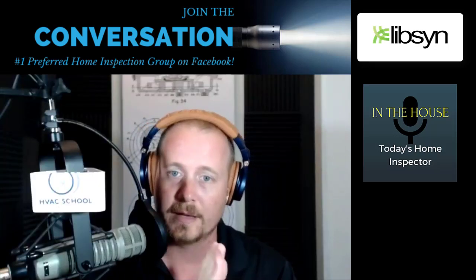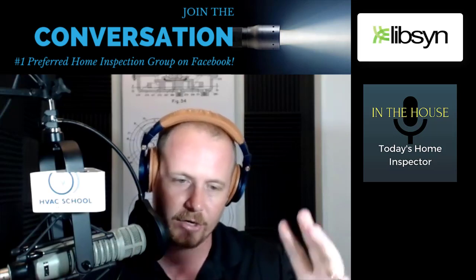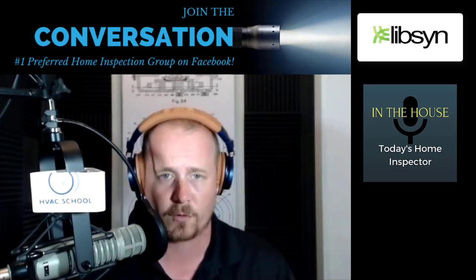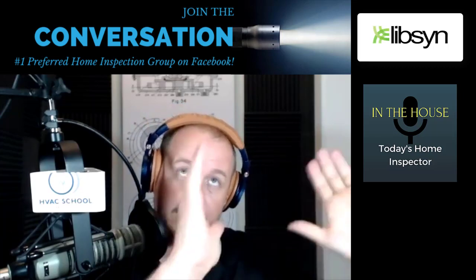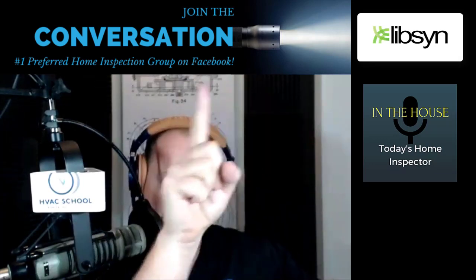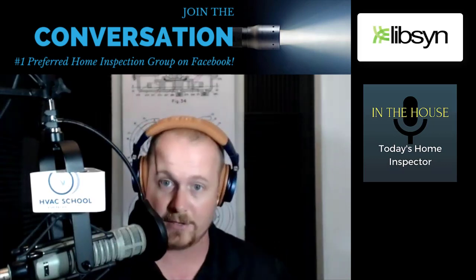So let me distinguish. A thermal imager has more value than a spot thermometer. With a thermal imager, you can look at something and see a good signature. A perfect example: I did a video just the other day of a full building performance analysis on a 12,000 square foot home. We're looking at the underside of the ceiling, at the boots where they attach to the ceiling, and we can see this pattern of low temperature around the vent on the drywall. Well, that tells you something right there.